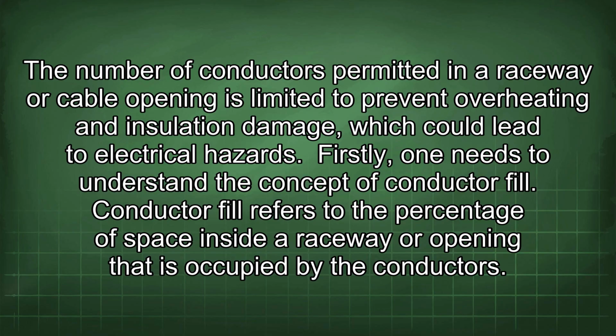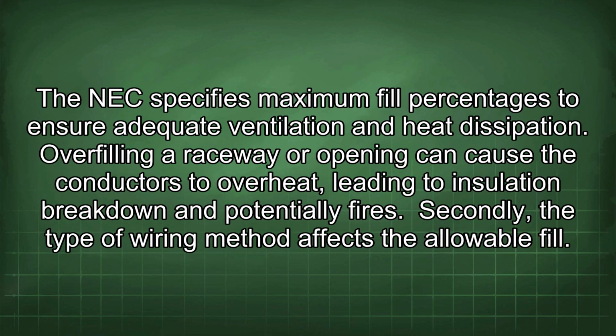Firstly, one needs to understand the concept of conductor fill. Conductor fill refers to the percentage of space inside a raceway or opening that is occupied by the conductors. The NEC specifies maximum fill percentages to ensure adequate ventilation and heat dissipation. Overfilling a raceway or opening can cause the conductors to overheat, leading to insulation breakdown and potentially fires.